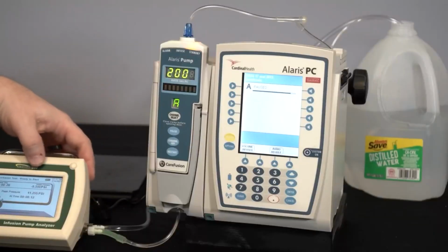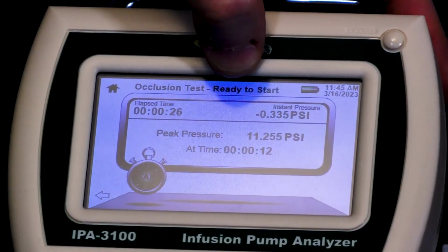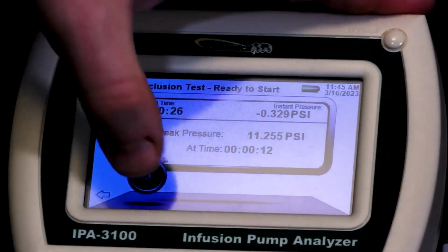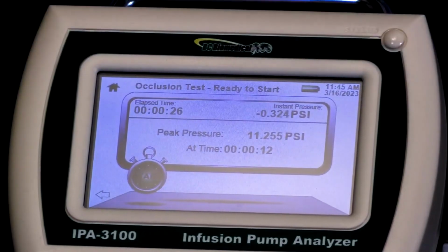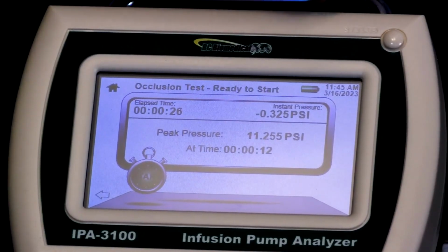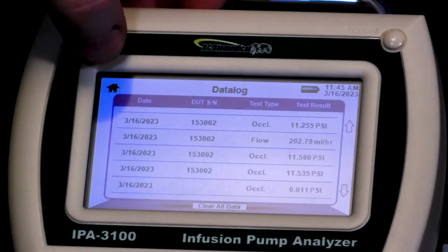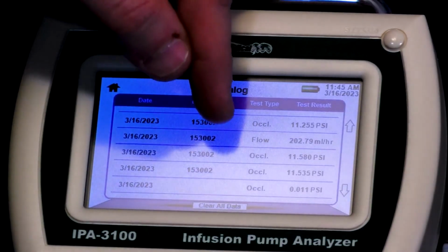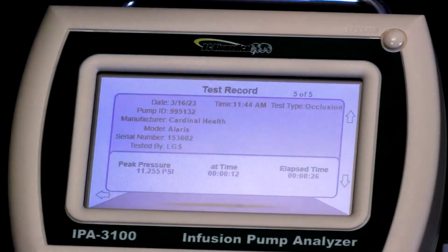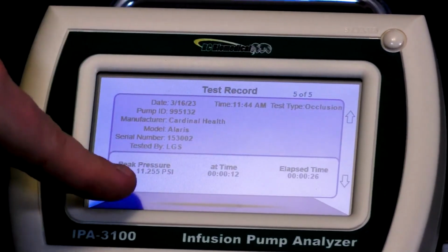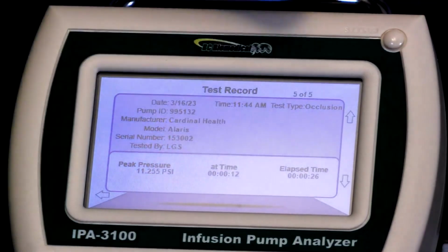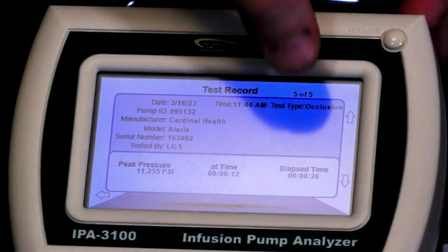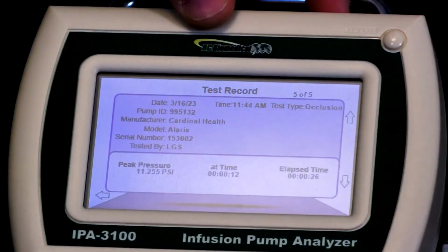So now we can see the test is complete. It's ready to start a new test. All I would need to do is press the start button here and start my infusion pump, and it would run a new test. But what I'd like to do is just take a look at the data log and see the test that just ran. So I can look at that record here, and we can see it shows me the peak pressure, what time it occurred, and how long the test ran completely, the elapsed time.